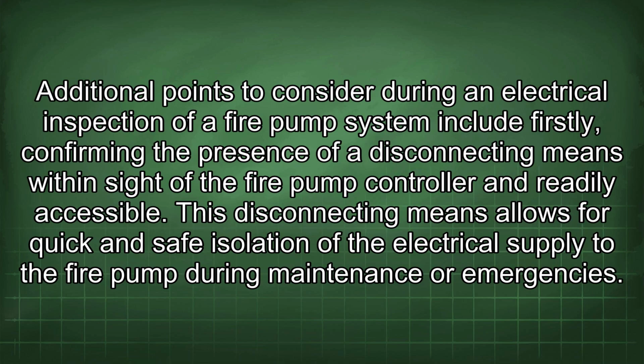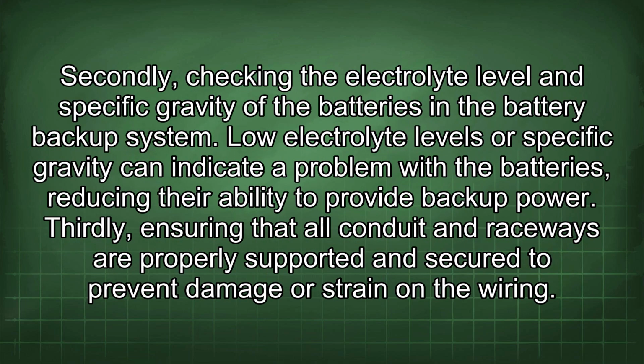Additional points to consider during an electrical inspection of a fire pump system include: firstly, confirming the presence of a disconnecting means within sight of the fire pump controller and readily accessible. This disconnecting means allows for quick and safe isolation of the electrical supply to the fire pump during maintenance or emergencies. Secondly, checking the electrolyte level and specific gravity of the batteries in the battery backup system. Low electrolyte levels or specific gravity can indicate a problem with the batteries, reducing their ability to provide backup power.